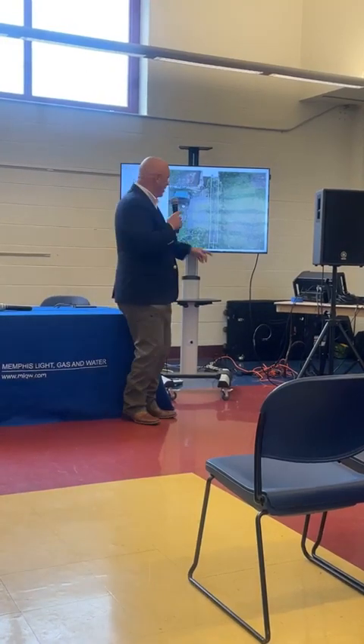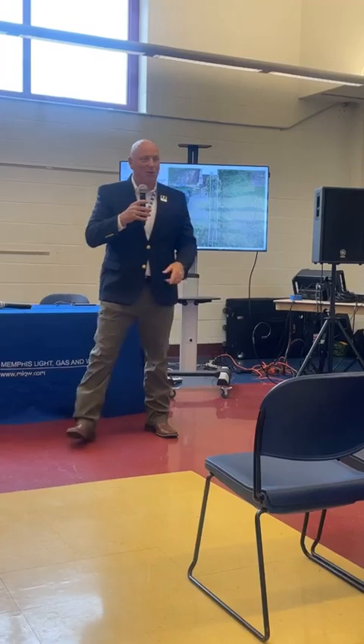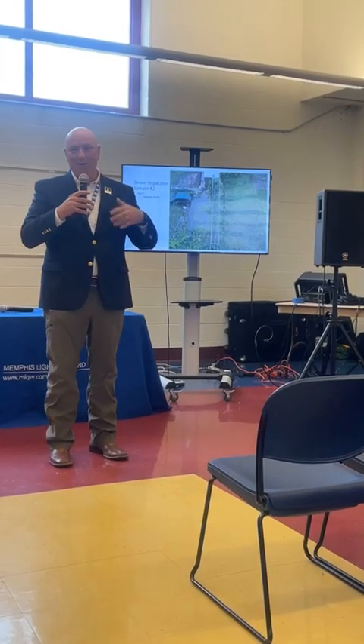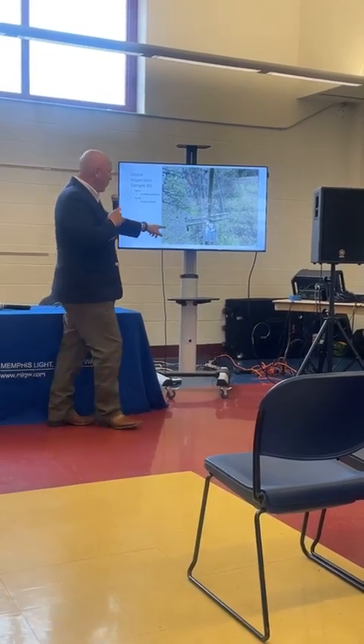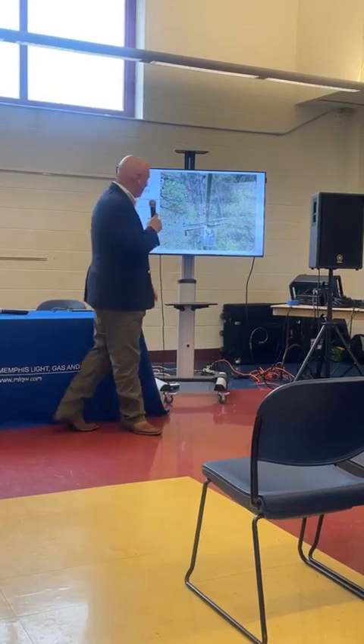Vegetation, this is what we talked about. There's actually a pole here. You can't really see it because it's so covered with vegetation. That will also put the system at risk for increased outages because that vegetation will short that out. Next. Here's another sample inspection that is pointing out this transformer has failed and we have to go fix it. Next.